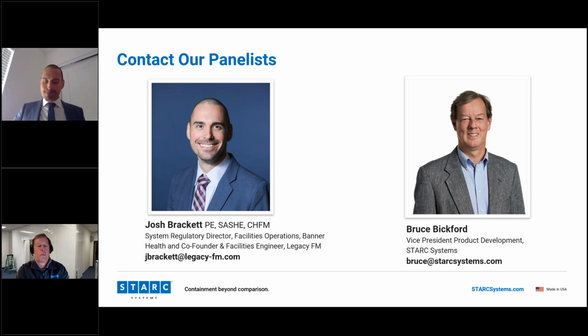Josh, first question is for you. Since you were referencing the 2009 edition of NFPA 241, would we also follow the older edition of NFPA 51B? Yes, I believe, I don't think that NFPA 101 has a direct reference to NFPA 51B. I have it pulled up right now, so let's check. It does not. So yes, you would have to follow the edition referenced in NFPA 241.